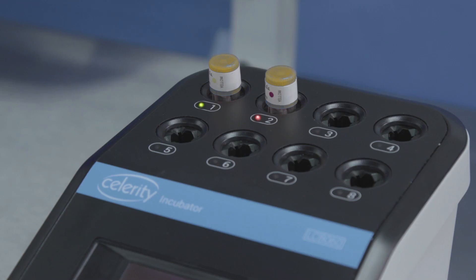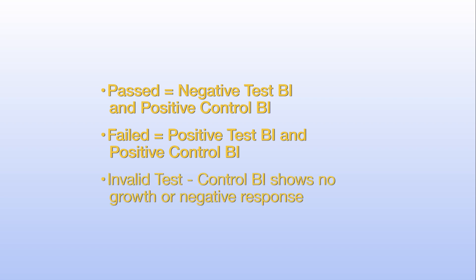The testing passes if the process BI is negative for growth and the control BI is positive for growth. The testing fails if the process and control BI are both positive for growth. If the control BI demonstrates a negative response or no growth, the results are invalid and testing must be repeated.